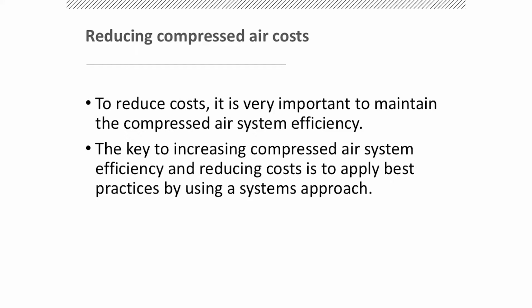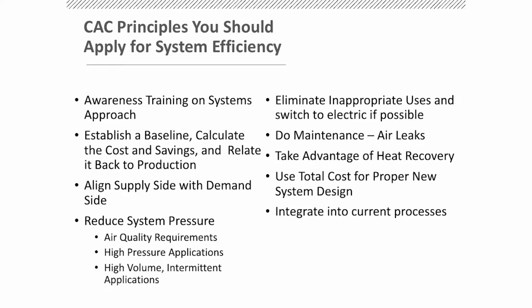So we're going to reduce the cost of compressed air. The main thing is to take a look at the system efficiency and take a systems approach, and that's really all the Compressed Air Challenge training has been about. The principles you want to be aware of: you want awareness, you want to establish the baselines, which you are very familiar with, and you want to calculate cost and relate it back to, I put production here, but it doesn't matter. Whatever the facility measures their actual goals in, put it back to that, because now it puts it on every single operational cost that they look at. Whether it's a cost per unit, per square foot, or an occupancy rate, doesn't matter what they're using. If they have some kind of cost that they're trying to reduce, it puts it in terms of every other single piece of objective that they have.